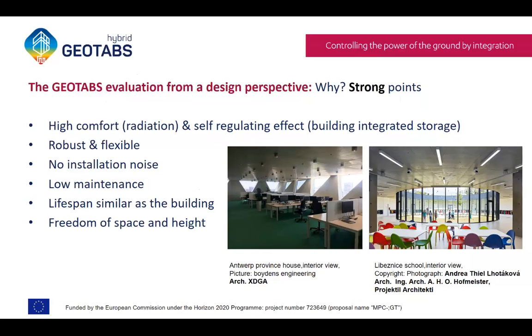On top of that, you have the self-regulating effect. It's a little more difficult to assess with standard methods, but briefly: if you have a concrete slab with a big inertia of heat or cold, at a temperature close to the room temperature, say 2 to 3 degrees difference - so if your room temperature is 24, the slab surface temperature is about 21 - then if the loads increase, the sun comes out and the room temperature rises slightly, the delta T between the slab and the room increases too. That immediately increases the emission from the slab to the room. So it's really regulating and managing the gliding of the temperature upwards or downwards.